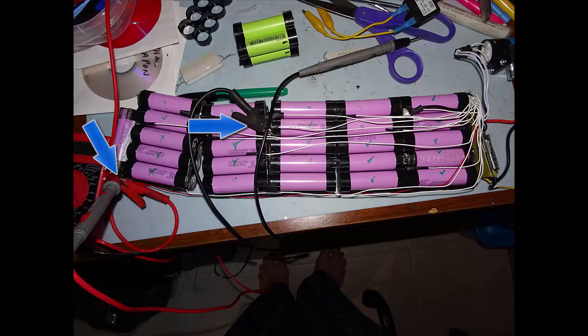And now you're looking at 6 times 4, 24 volts. You want to force charge these to 24 volts. That's how you charge the lower half of the battery with a 30-volt power supply.